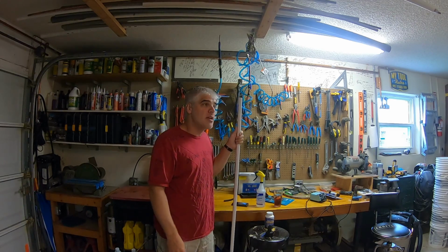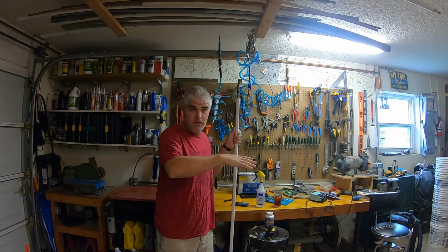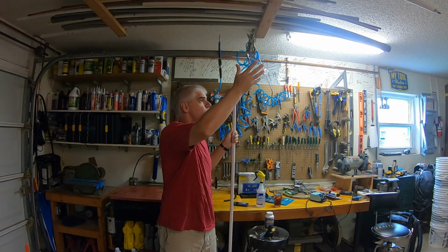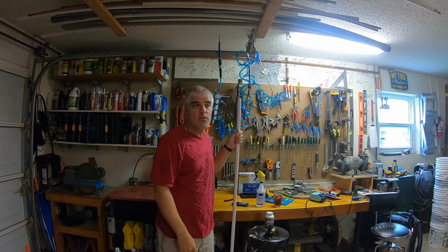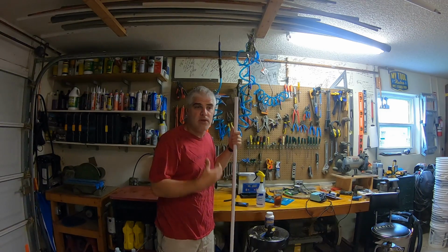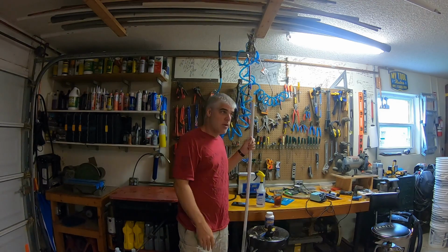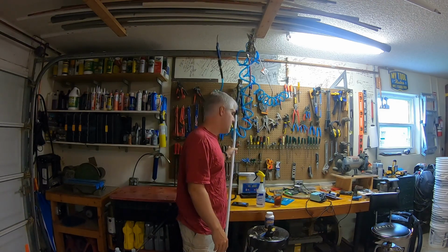If you're not so lucky, the primary pan will overflow, fill the secondary pan if you have one, and if your air conditioning is mounted in an attic, then the unit will overflow and perhaps collapse your ceiling. That happened to one of my neighbors not too long ago. So you want to keep an eye on this. Again, hopefully you have a drain switch. If you don't, I would highly recommend picking one up.